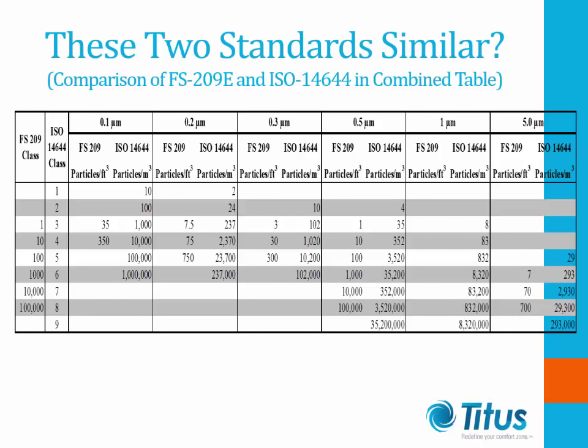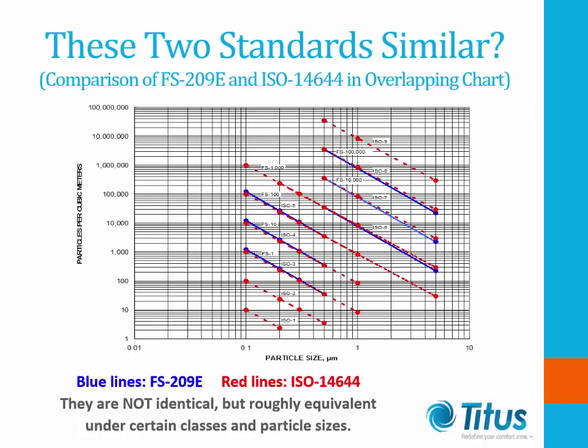Federal Standard 209 has six classes defined in five particle sizes: 0.1, 0.2, 0.3, 0.5, and 5.0 microns. ISO has nine classes — two classes cleaner and one class dirtier — defined in six particle sizes, including an additional 1 micron size. If we overlay the two standards on a chart, blue lines represent Federal Standards and red dashed lines represent ISO standards. These two standards are not identical, but in the industry we roughly consider them equivalent under certain classes and particle sizes.